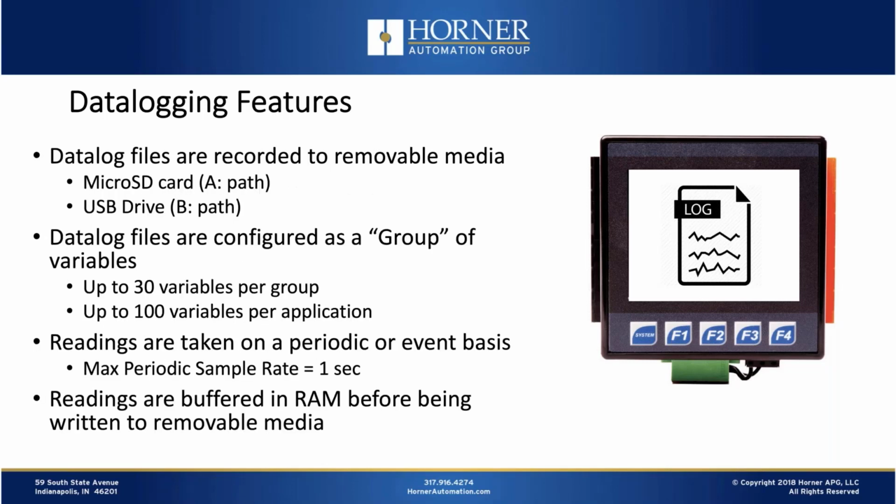Okay, so from a features standpoint, data log files are recorded to removable media, and that can either be a micro SD card plugged into the micro SD slot, which is considered drive A with our products, or the default drive, or you can actually data log to USB if you've got a USB drive plugged into a full-size A port on all of our products that support those particular ports, and that's considered the B path to log to that particular drive.